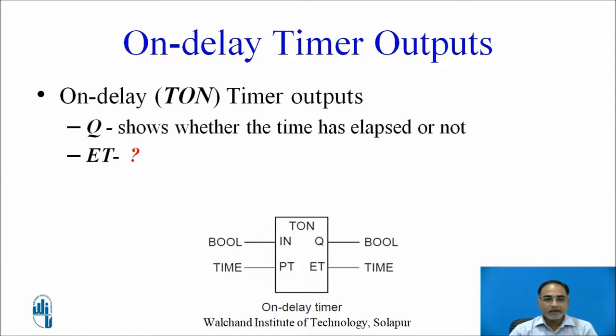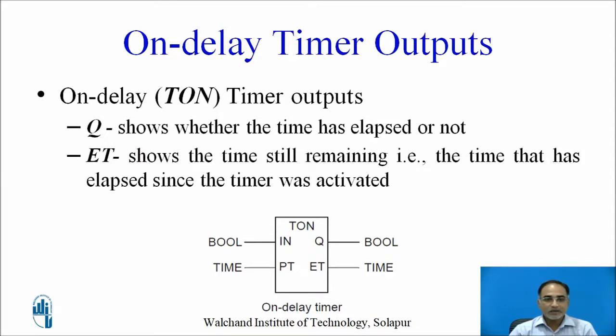Q shows whether the time has elapsed or not. ET stands for elapsed time — it shows the time that has elapsed since the timer was activated. The data type associated with ET is time, so you get the current timer value in seconds at ET, while the data type associated with Q is boolean.